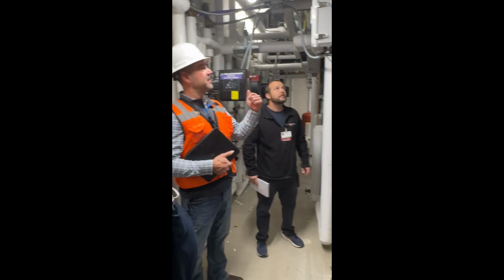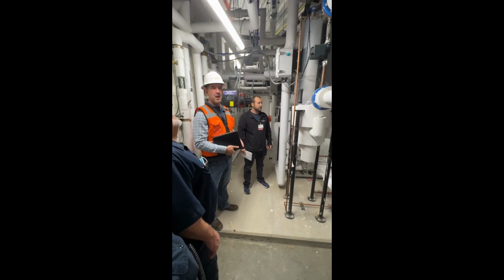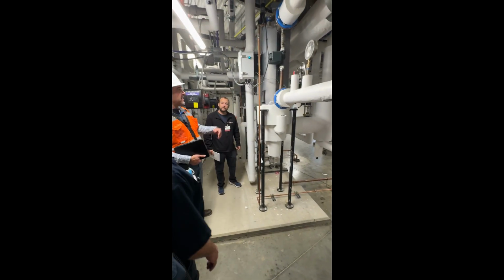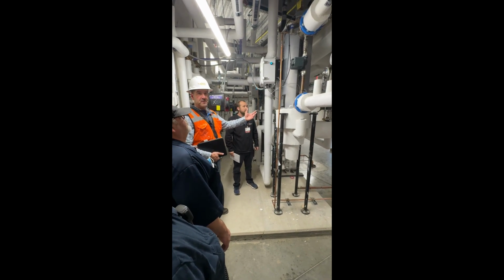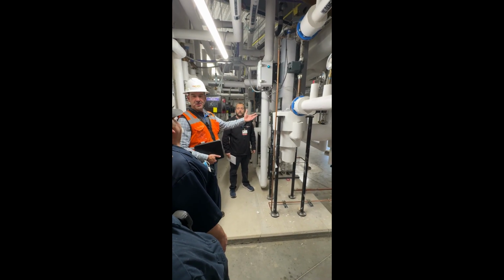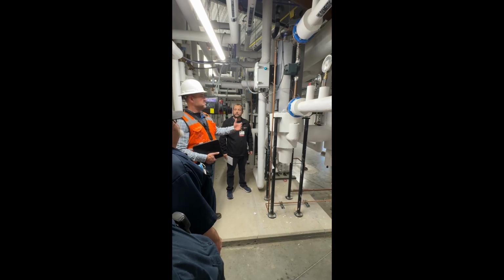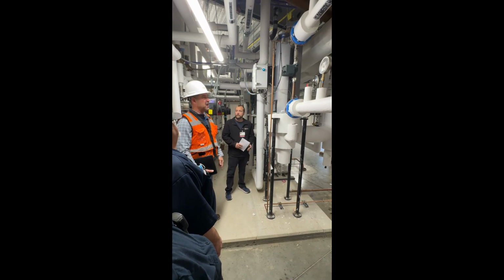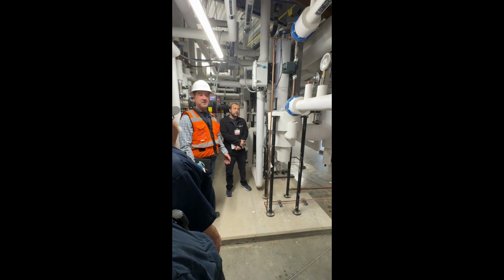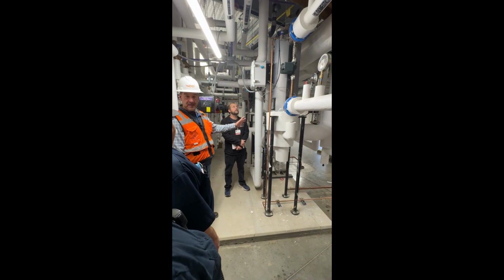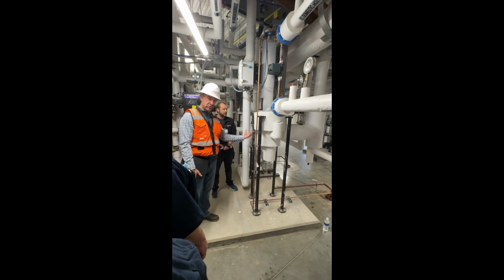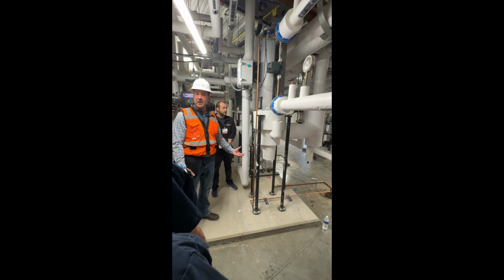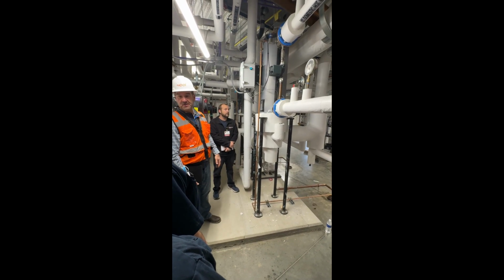Okay, so these are diversified heat transfer, steam to water, domestic water heaters. So you've got steam on the shell side, water on the tube side. Stainless steel shell, copper nickel tubes. Should last 7 to 10 years before you need to pull the tube. Actually, to clean the tube, this entire bottom housing drops out, so it's very simple to clean. You don't have to pull anything on the shell side.